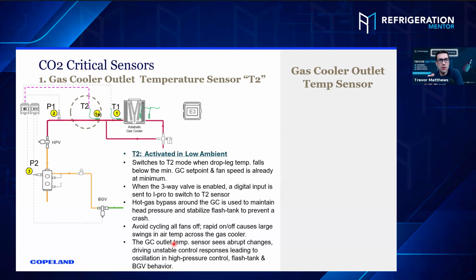I love that. And that's so important because this has nothing to do with really CO2. That insulation outside, condensing units, for example. When I'm doing a training talking about a condensing unit on the roof, and the pipe runs 40 feet across the roof and then down into the walk-in box and it's all insulated, but if it's all falling off, that is not good. It's going to kill that Copeland scroll inside that condensing unit because of all that heat it's picking up. It's similar here, those UV rays will beat on insulation, on wiring.